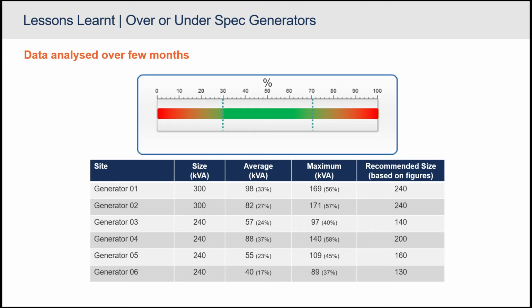Let's focus on number 3, for instance, running on average of 24%, which is below the 30% threshold, which is really bad for that generator. It will dramatically reduce the asset's expected life. And at most it's running at 40%.